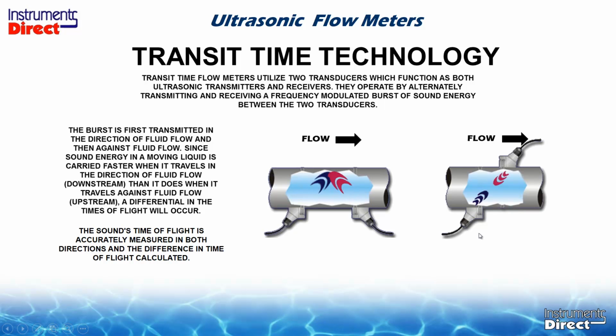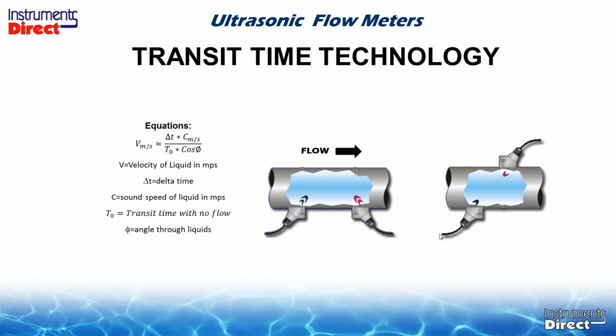The transducer on the left sends a sound burst across the pipe to the transducer on the other side to measure how long it took to get from the first transducer to the second transducer, or the transit time. At the same time, the second transducer sends a sound burst back across the pipe to the first transducer, and because it's going against the current, it takes a longer period of time. So the faster the flow rate, the greater the differential in transit time between the two transducers. This differential transit time is the coefficient we use to calculate volumetric flow, for example, GPM, gallons per minute.